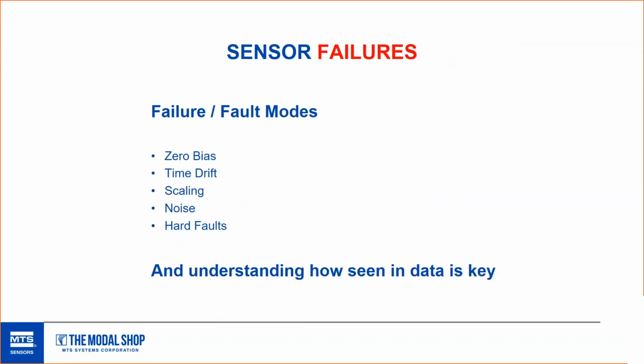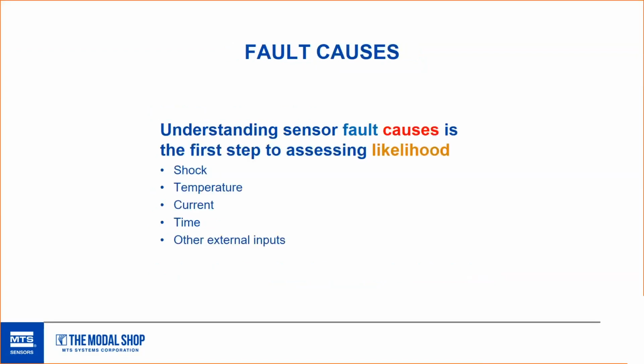It was presented, I don't know, maybe a decade ago, and it should be viewed as a Bible when you're considering sensor failures. But if there's bias faults, which mean zero drift or shift, any change in output over time that's completely unrelated to the input environment or load. If there's any time drift, which is any change in sensor output just based on time. If there's any scaling, which is the variance in transducer output to the input ratio. Any noise or complete hard faults where it's just measuring something completely off, almost like by a DC value. And understanding how this is seen in the data is key. This is really what makes people experts in their field, that they're able to troubleshoot failures like this. Looking at the fault causes is really one of your first steps into assessing likelihood. How often do you think you may have a shock event or a temperature event?